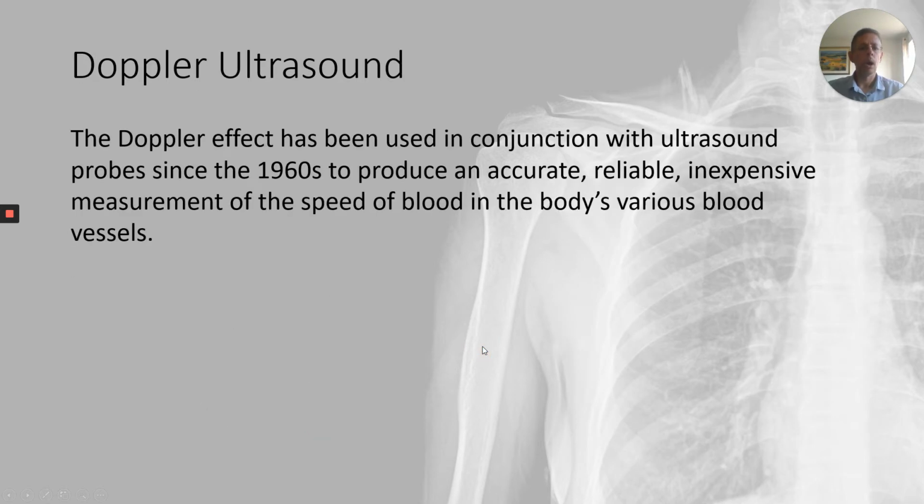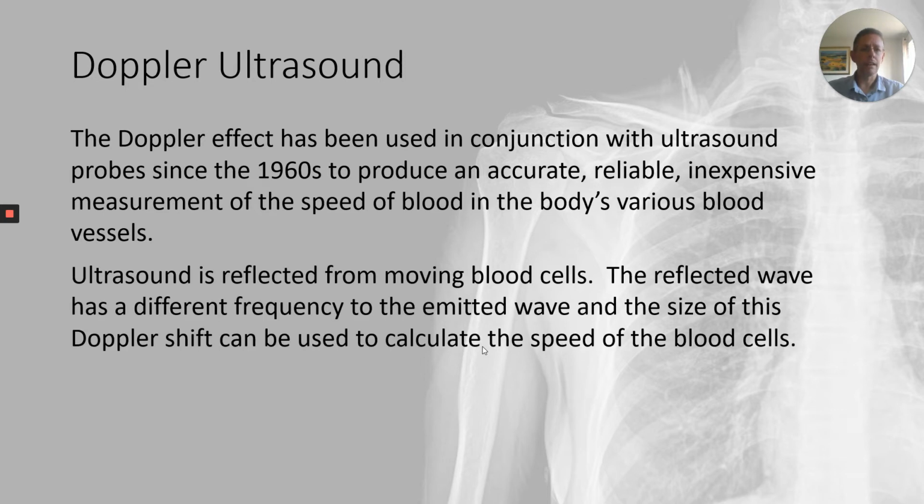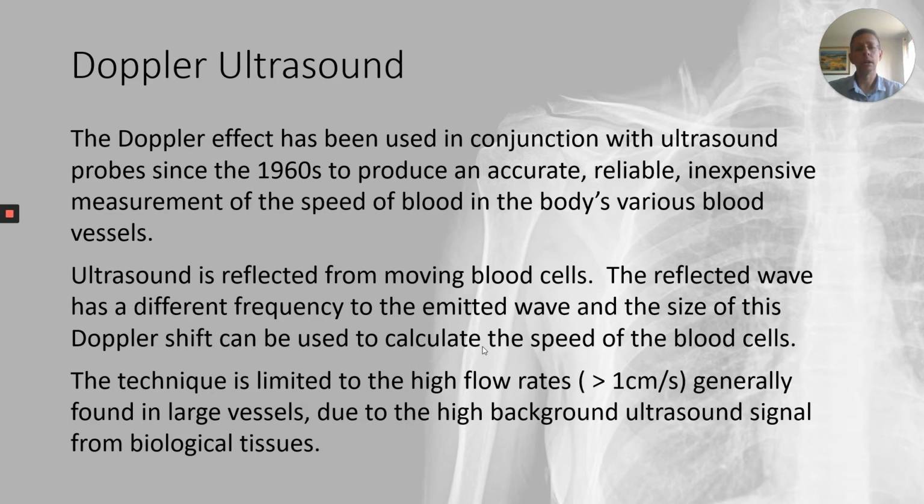So it is, like ultrasound itself, a reliable and well-tested technology that has been around for 50, 60 years. It doesn't have a very high resolution, so it tends to only work if the blood is traveling quite fast. So we need to focus on the flow of red blood cells in arteries, and we're going to use the Doppler effect to try to work out how quickly the blood is traveling.